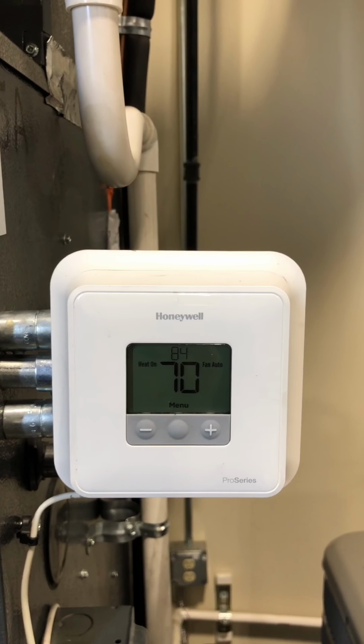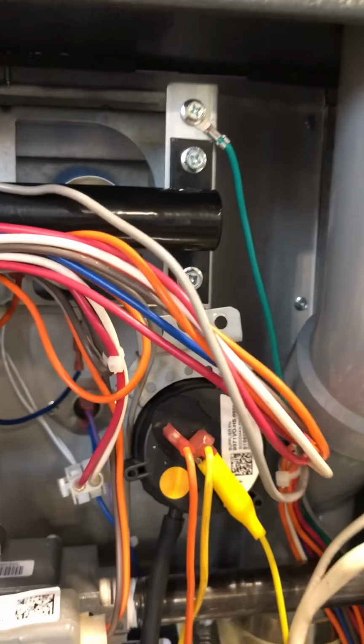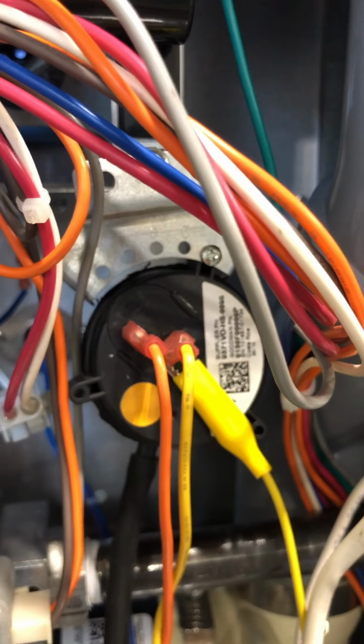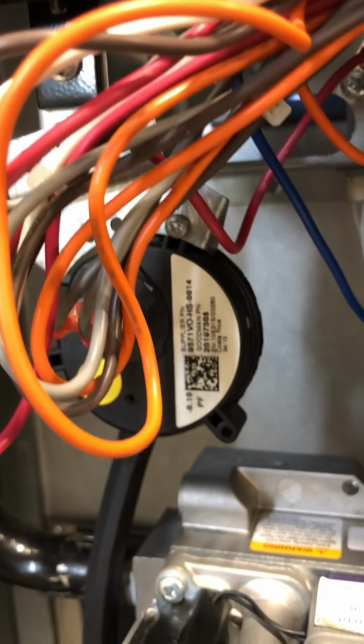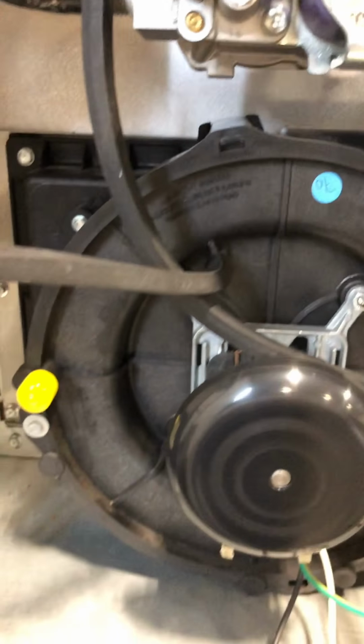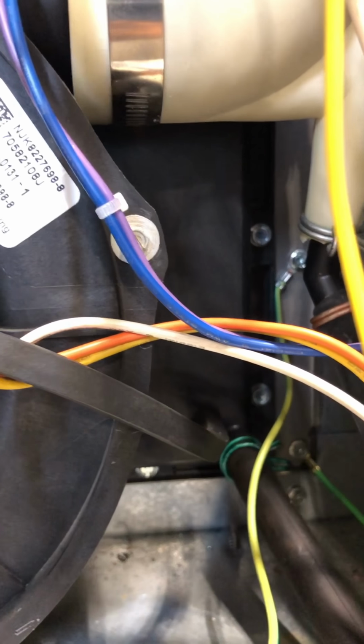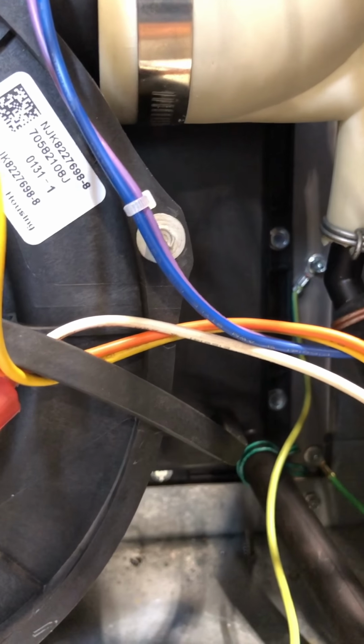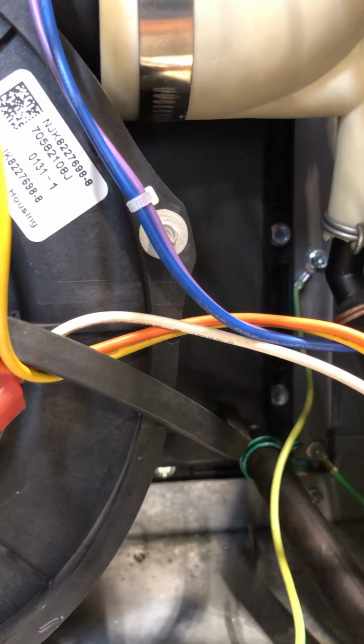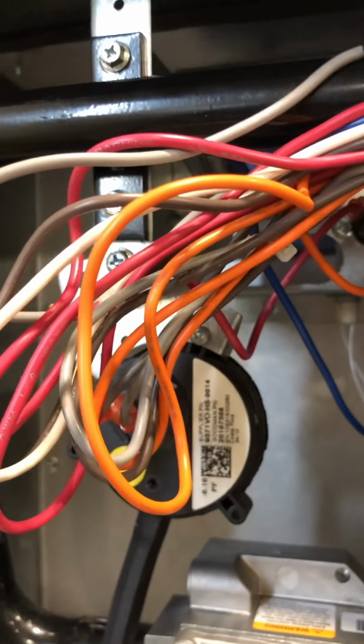Let's go over it again. Call for heat. Furnace control board will verify that that pressure switch and the other pressure switch, which we haven't talked much about, but this is a 90% furnace. Okay, so we're going to condensate. So that one is actually hooked to down there at the bottom of the collector box, where water's draining out of there. If we get a plug and water starts to pile up, we won't be able to pull a vacuum through that hose, and this switch will open up and cut power.